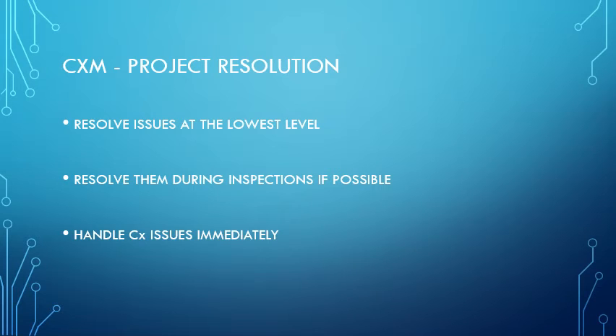The resolution approach for the commissioning process is to resolve any issue at the lowest level. We try to solve any issues firstly with the subcontractor, and then go to the main contractor before going to the consultant and building owner. Also, we have to resolve them during the inspection if possible. If it is a small scale project and it can be done on the day, just go ahead and handle any commissioning issues immediately.